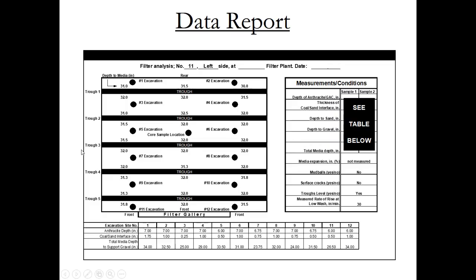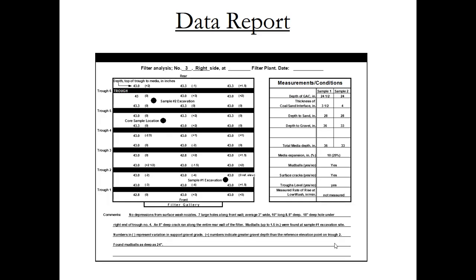This is just an example of a data report from a filter inspection. It shows the freeboard, where there were excavations, the anthracite depth, and total media depth. You can see this is uneven, which is an indication that the gravel is uneven. This is another example of a data report showing similar information — this one also shows the bed expansion, which was 29%, which is actually pretty good.